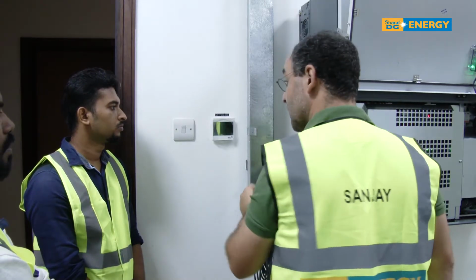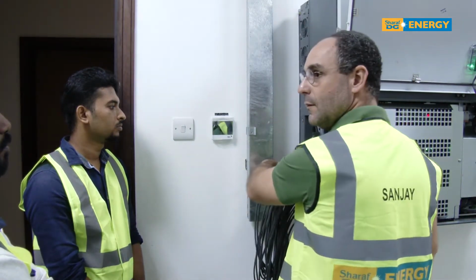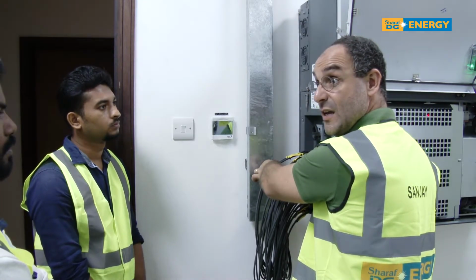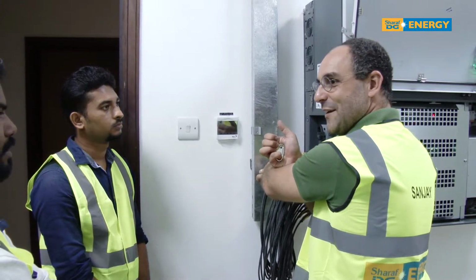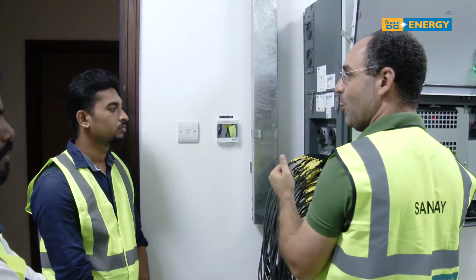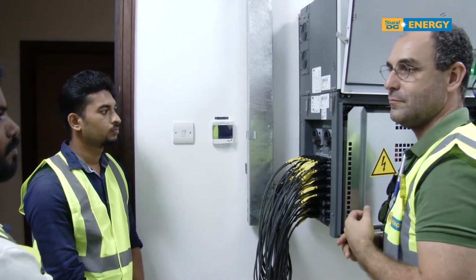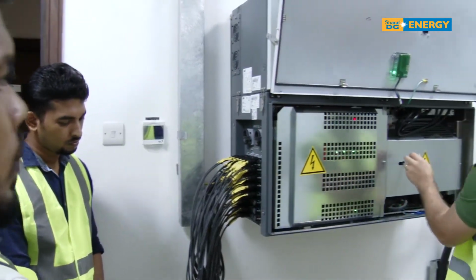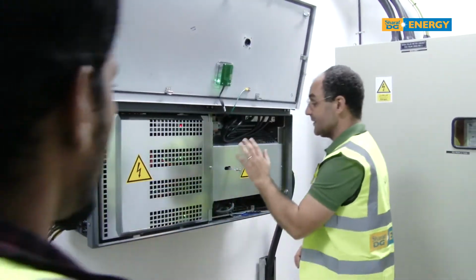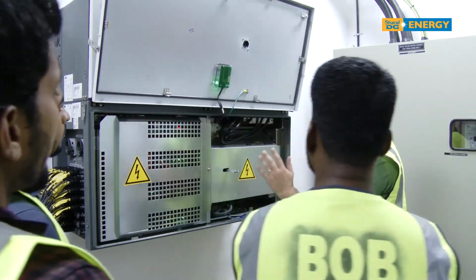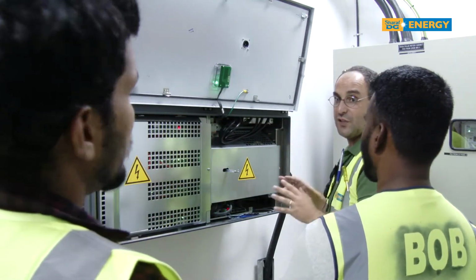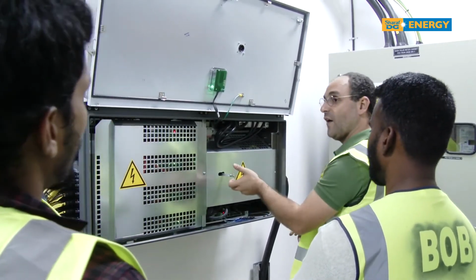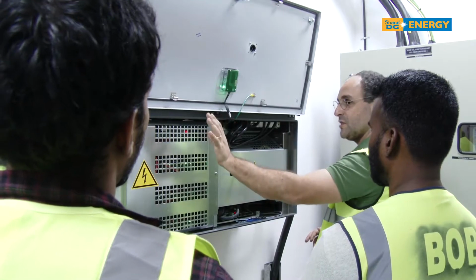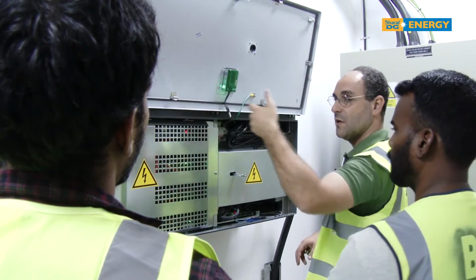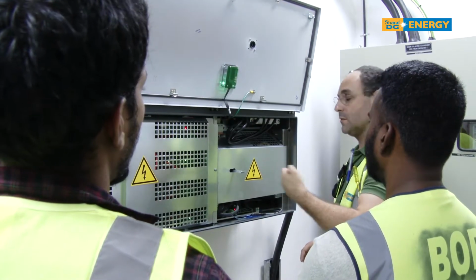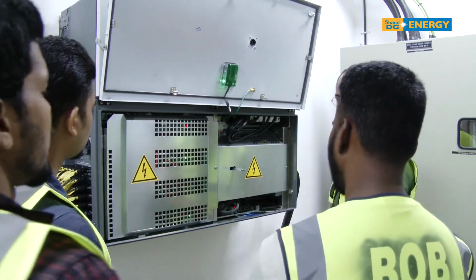First, clamp meter. Measure here with the clamp meter, current zero on the meter, I'm safe, go. This side is the same, you have the isolator, these are the DC switches, this is the AC isolator. So one way to replicate this for safety is: off isolator, if you want to work on the DC side, off isolator, off DC switches, measurement tool, zero amps, go, work.